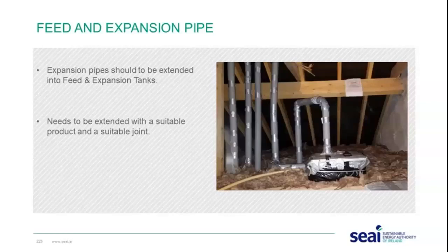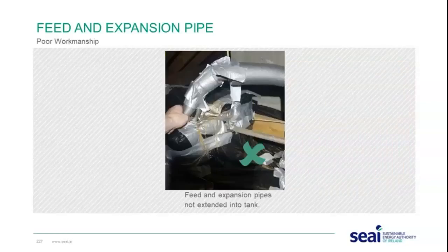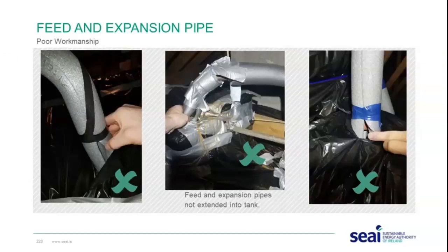Feed and expansion pipes should be extended with a suitable product and a suitable joint such as copper, and the pipe should be terminated below the lid of the tank but not below the water line. A poor workmanship example shows feed and expansion pipes not extended into the tank — in one inspected job, water was overflowing down onto the insulation at ceiling level and leaking through to the plasterboard ceiling below. Proper extension into the tank could prevent that callback.